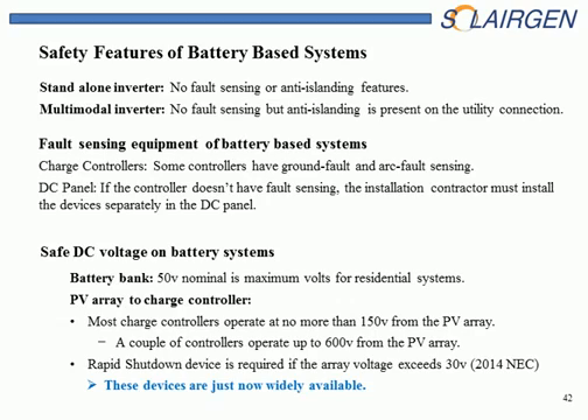How about safe voltage on the battery system? Well, with residential systems, unless it's a completely enclosed battery system such as the Tesla Powerwall, which is not available yet, it's going to be a 50 volt system. So 50 volts is pretty safe. I've touched the terminals of the positive and negative and felt nothing, so that doesn't mean it's not potentially hazardous, because it is over 30 volts, but it's not inherently dangerous.